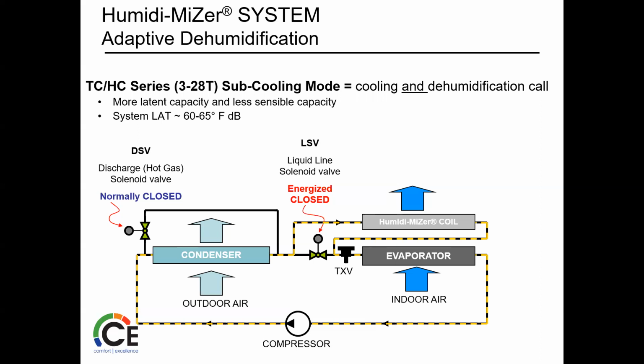Indoor airflow really doesn't change. Again, that's where we're removing things. So it flows through a subcooled evaporator at this point, where the air is cooled lower than normal temperatures and the moisture is removed. So instead of heating it like the older systems do, now we're doing it in a cooling mode, and they found that it's more effective.